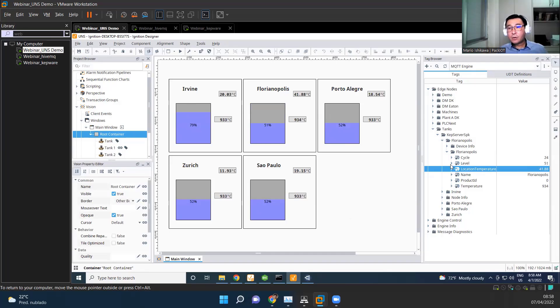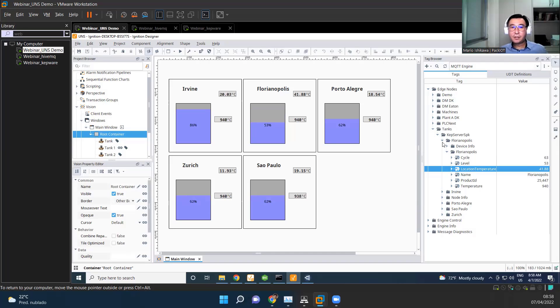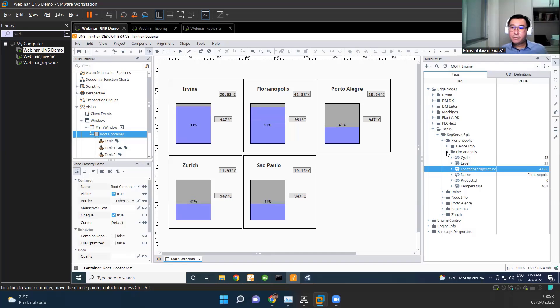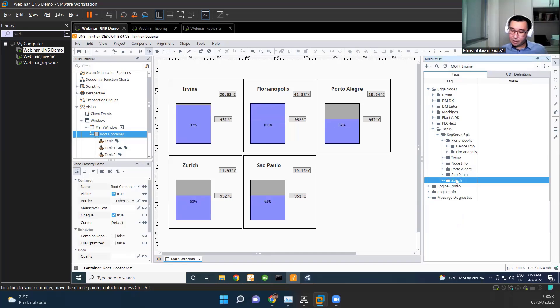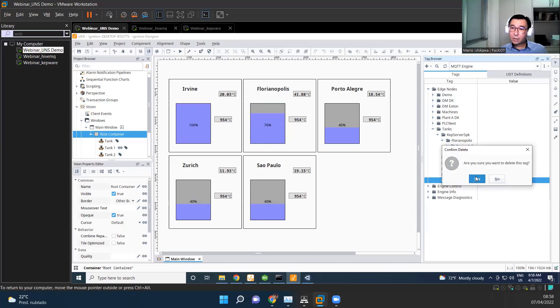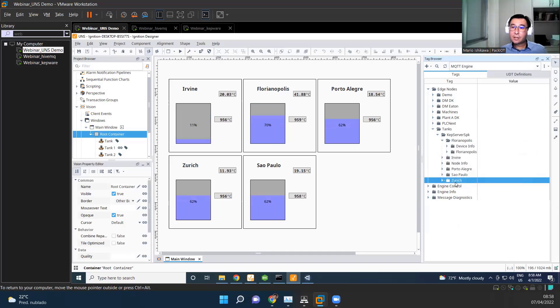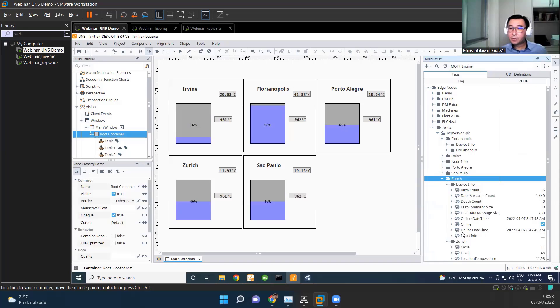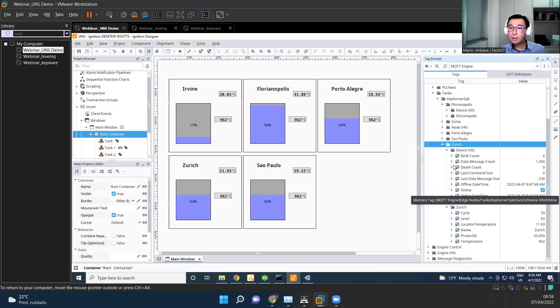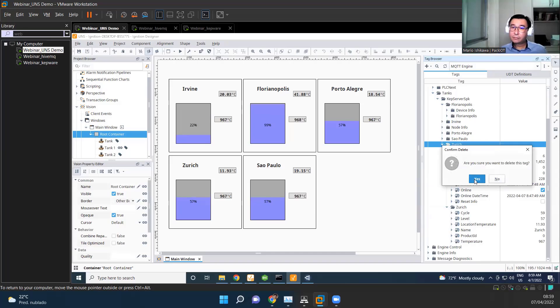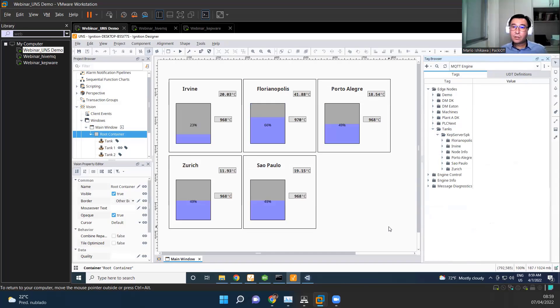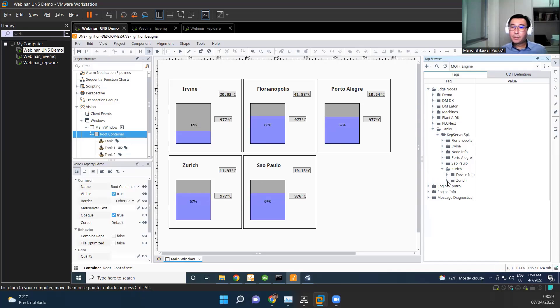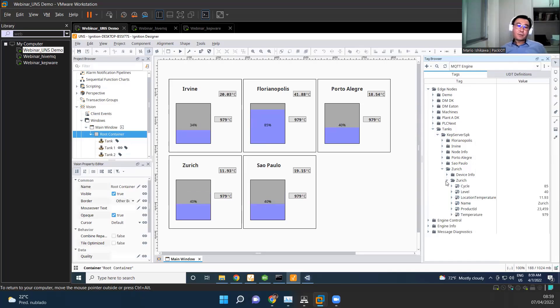But the important thing, we don't need to actually come here as we usually do on industrial systems, like taking a PDF or Excel spreadsheet, the reading. What's this register on Modbus? What does it mean? Is it temperature? And then we manually create tags here. For example, if you see, I'm going to delete Zurich here. And when I delete Zurich, look, I am literally really going to delete this entire folder that has several tags and properties. So I'm going to delete it. You see there, it created a short communication problem here, but it reappeared. So why it reappeared? Because of Sparkplug B and MQTT. So Ignition SCADA can understand Sparkplug B. So as it receive information of tags that it doesn't have, it will create, it will understand.